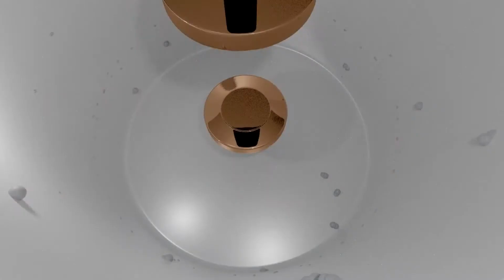It will come back because those gas molecules that were not combined or oxidized have been pushed out of between the contacts, and some of them have trapped behind the shield, trapped behind the bellows shield. They'll come back and accommodate in a few days or a few weeks, and the pressure will come back up a little bit. But it's not going to come back to where it was because we've destroyed enough free gas molecules that the pressure is going to be lowered between 1 and 1.5 orders of magnitude, which is going to be 5 years plus of additional service.